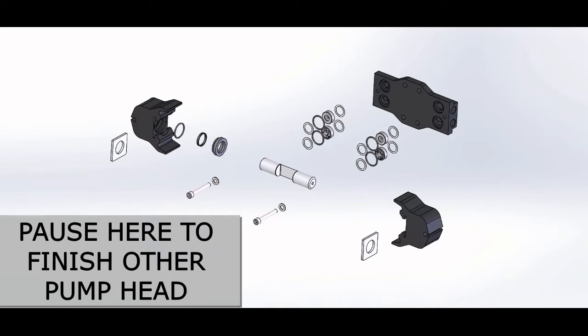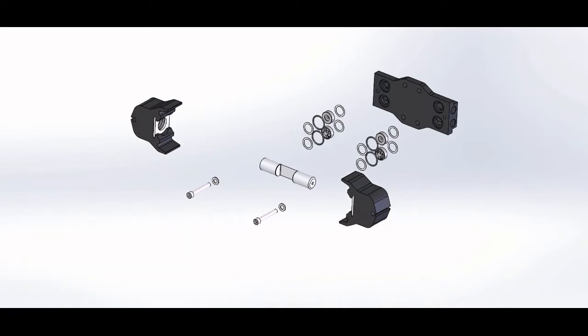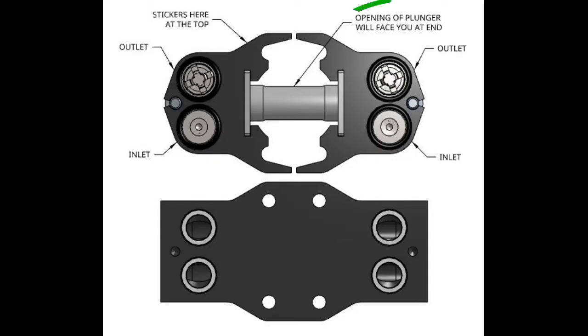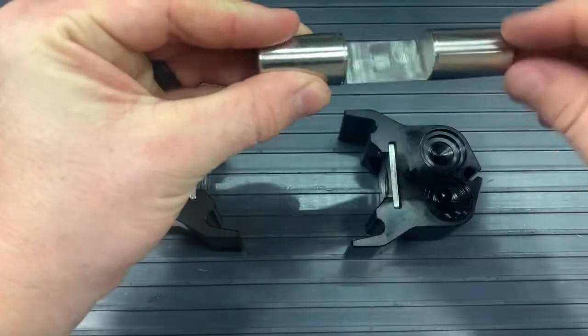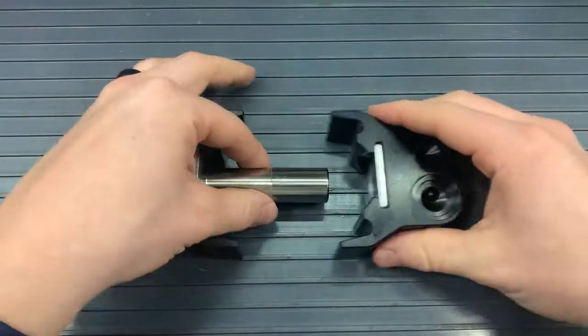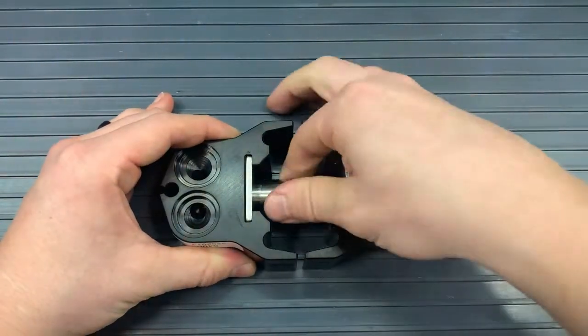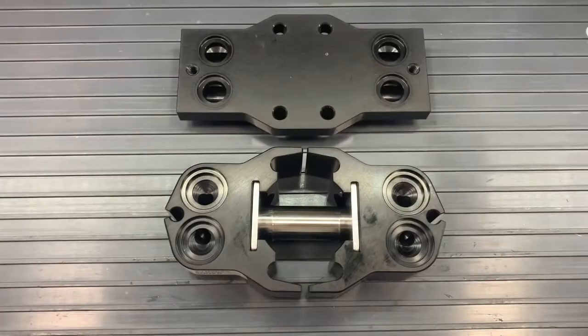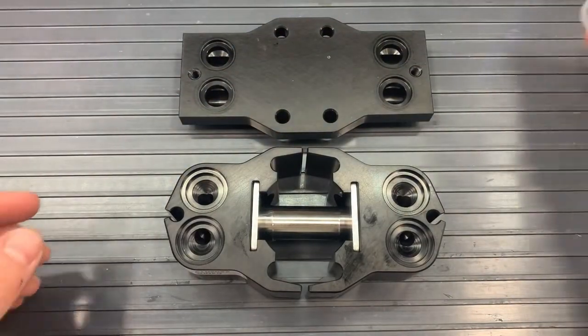Repeat these steps for the other head, and now we are able to put our new plunger back onto each head. The orientation is important. We want the opening of the plunger to be facing away from us. We do want it centered because when we eventually put our pump back onto our cam and our motor, it is important that it's centered so it'll fit on there. Now that we have our pump heads connected with the plunger, we will need our manifolds.